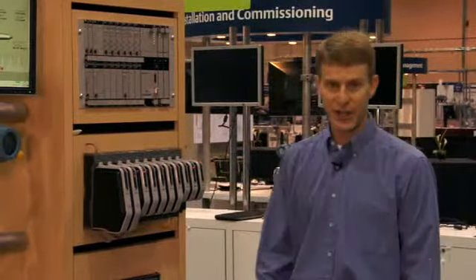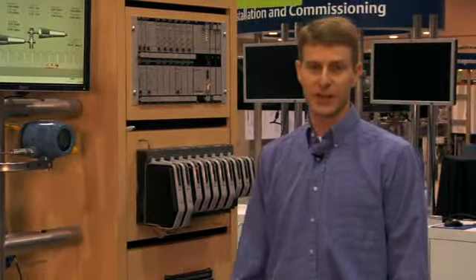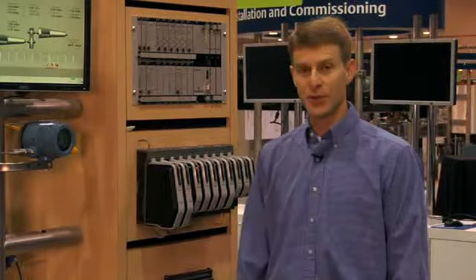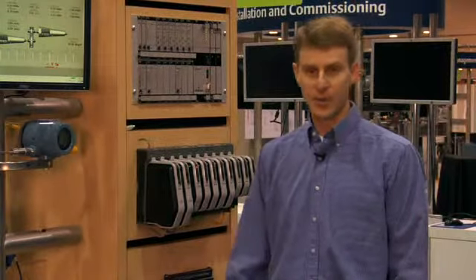So the second feature is that we use this FHX file to import the information into the Delta V. Once the information is imported into the Delta V, the control studio is automatically set up, all the function blocks are created, fan out blocks are created.